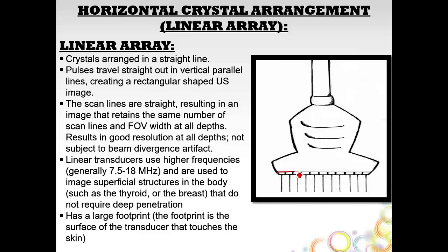And you can see here there's just a single horizontal row of crystals here, and they're arranged in a straight line. So every crystal sends out its own sound wave. So what happens is the ultrasound machine over here sends out an electrical charge, and the electrical charge hits the crystal, and the crystal changes shape, and it vibrates, and it emits a sound wave. And then that sound wave is going to go out into the body. It's going to hit a structure, and then it's going to return back to the transducer. And that returning signal we call an echo.